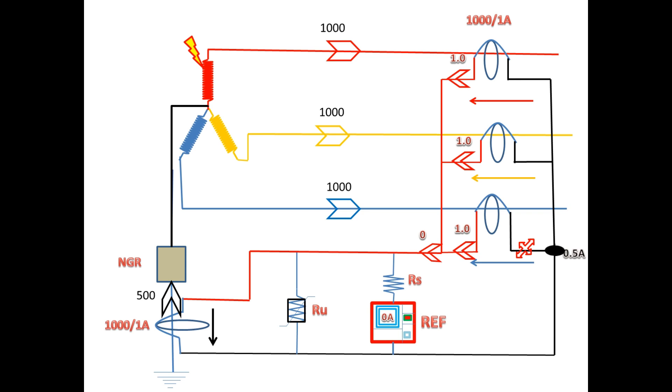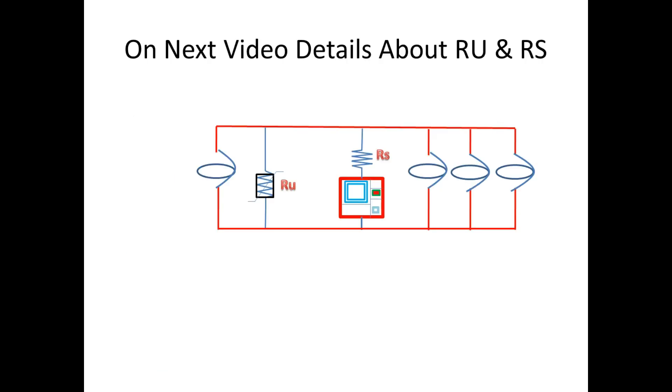The next path for current flow is the REF relay. So all the current enters the REF relay through the stabilizing resistor. Once it enters the relay, it will start to pick up and trip according to the relay setting. Once it trips the breaker, the fault will be isolated from the IN-zone of the REF.